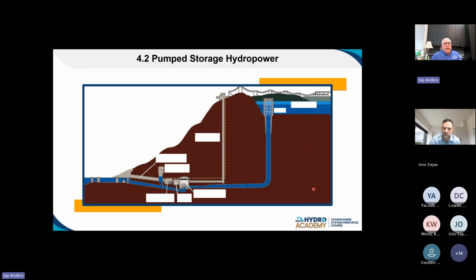What I would point out, and it's obvious once I tell you, is that there's simply a large elevation change between this lower reservoir and the upper reservoir. That's still the basic thing we rely on. Typically pump storage plants with greater than 600 feet of head is a really good number, and most have an elevation change closer to 1,000. It gets into the economics, but the calculation is the same: it's head and flow to figure out how much power you can get. If you can get this body of water, your flow, really high up in the air, you can get more power out through your powerhouse.